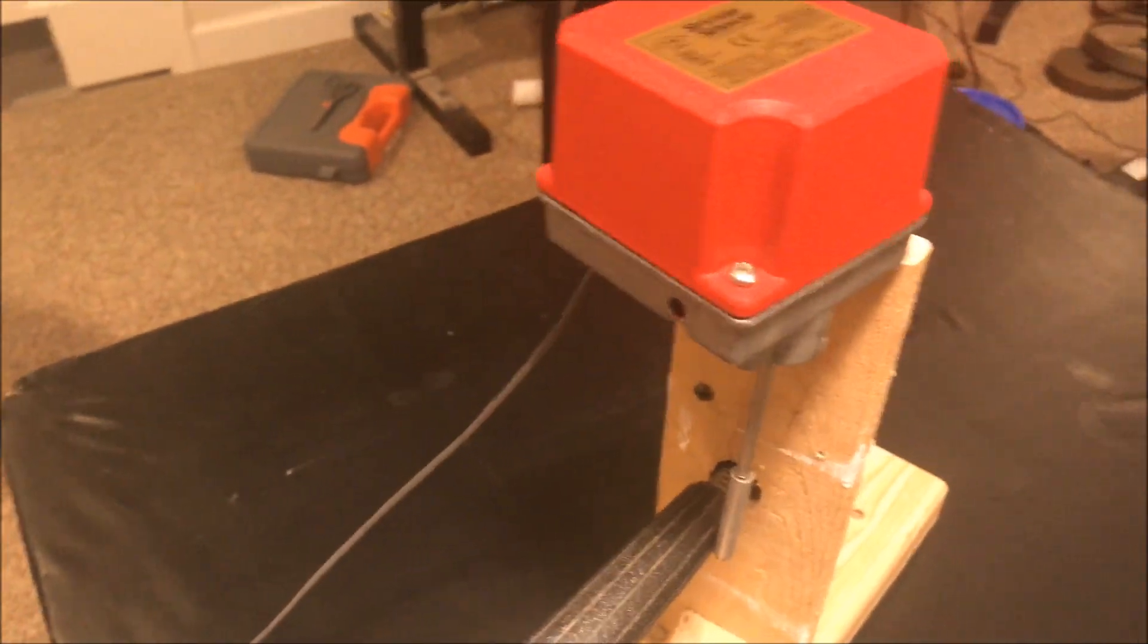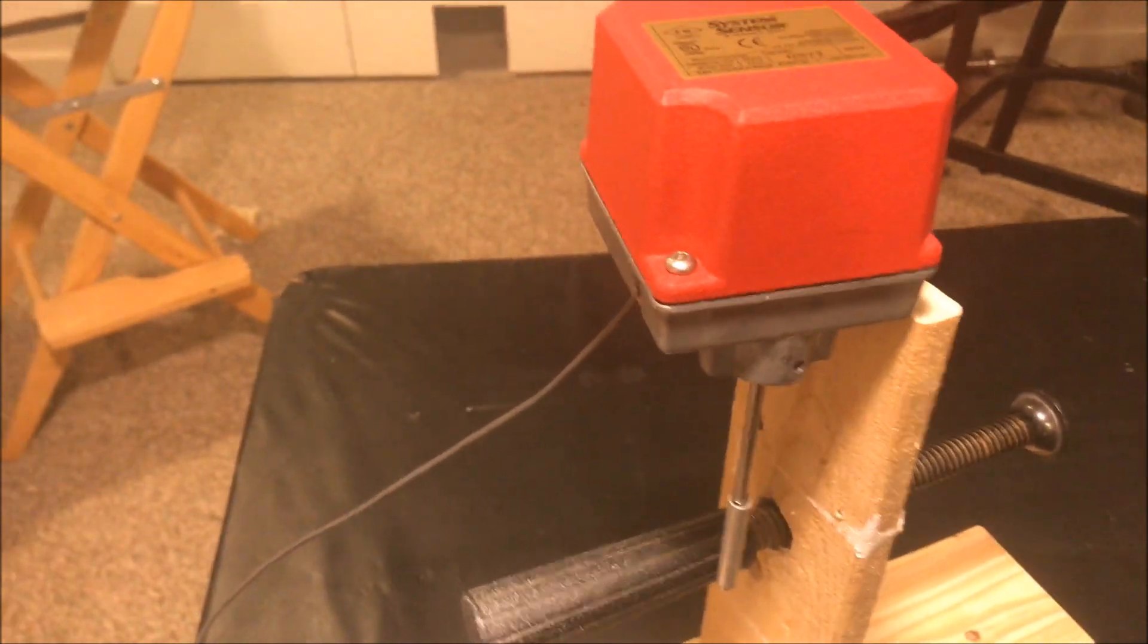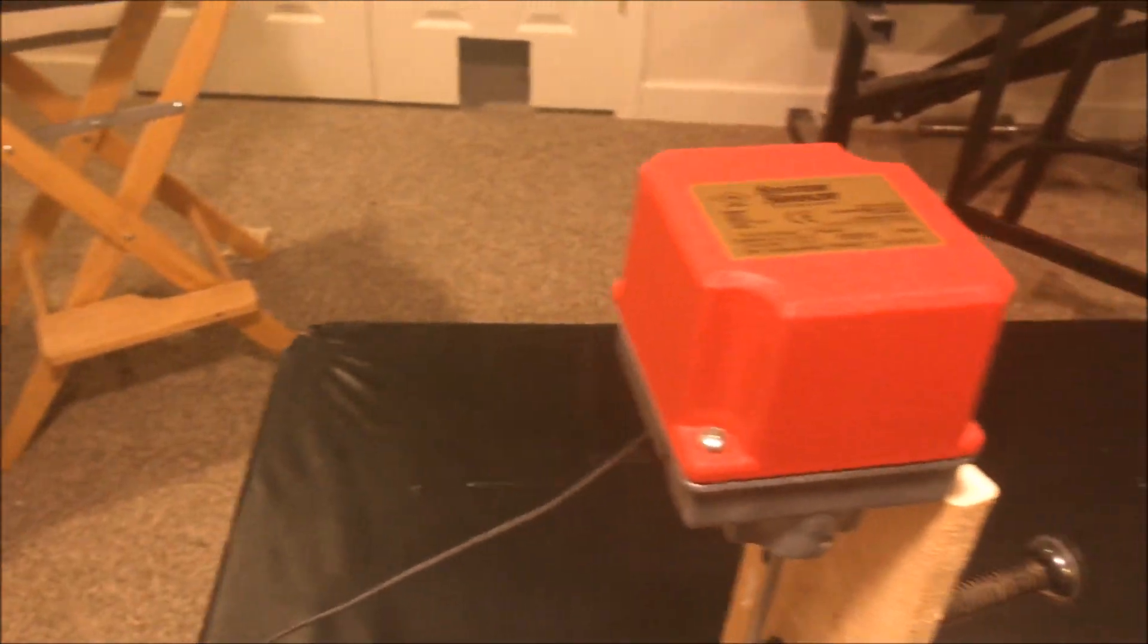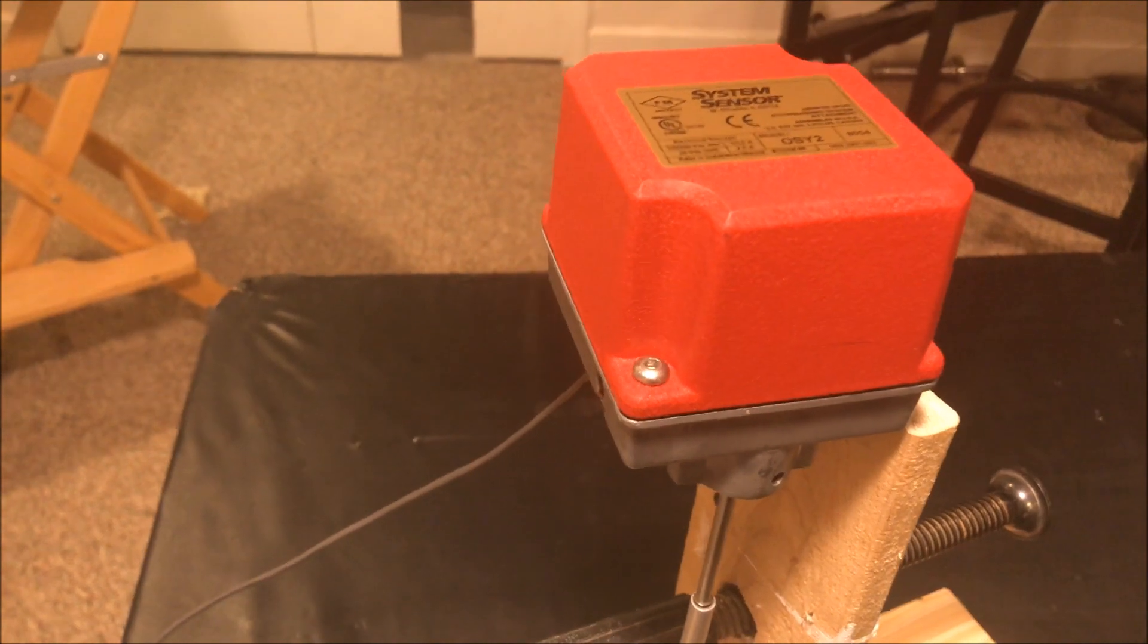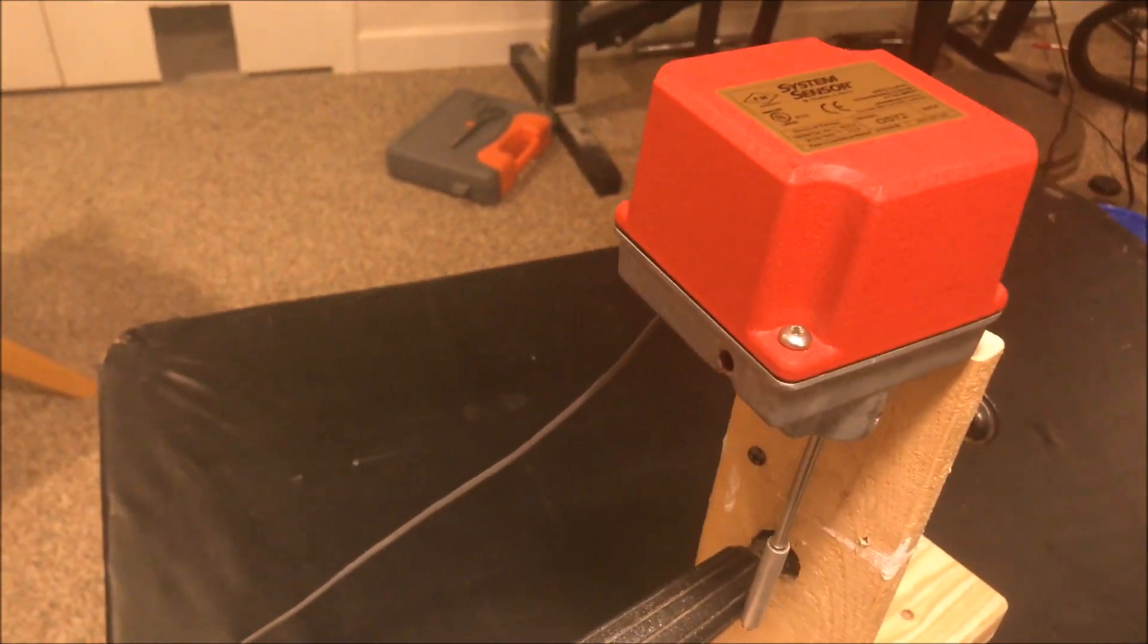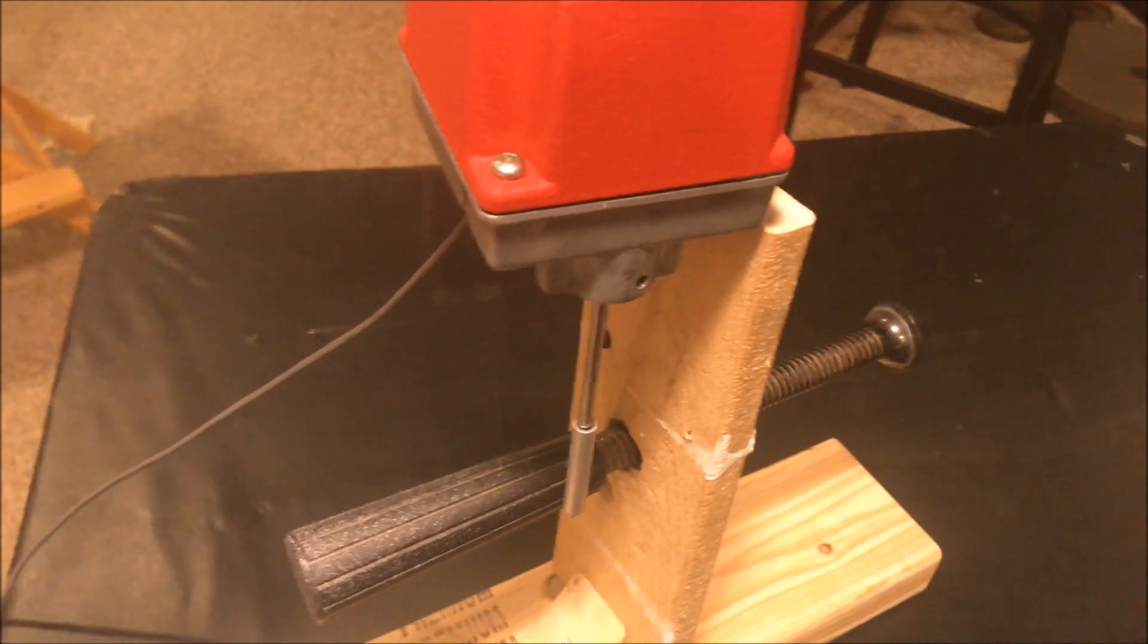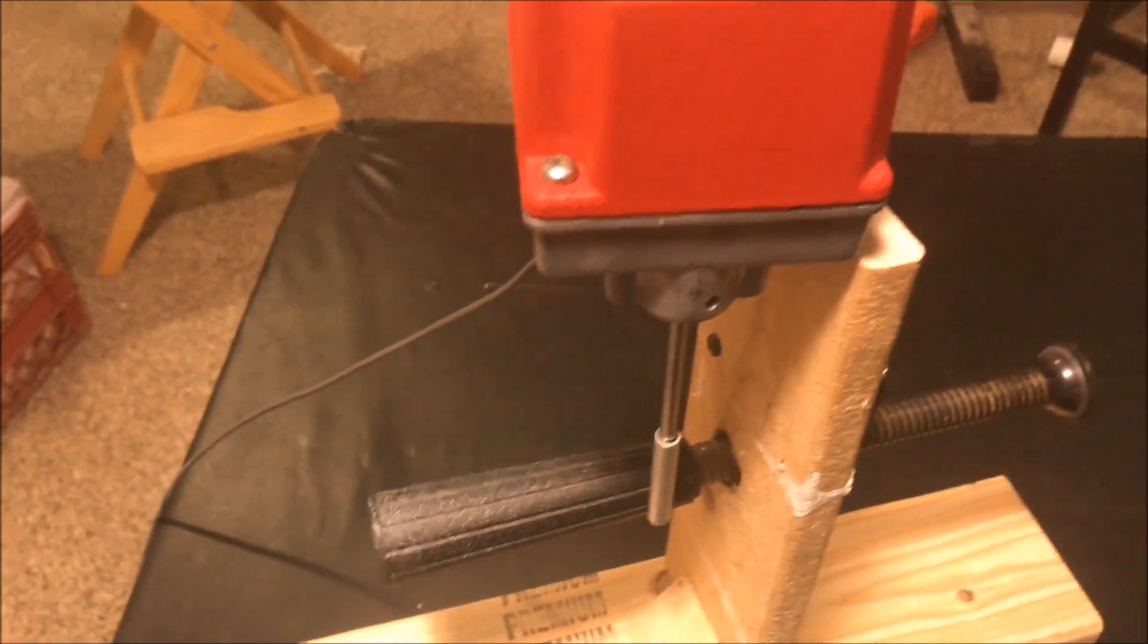Alright, so we got the switch back together. The panel is ready to go into supervisory, no alarms will sound. I know I have the key switch set for supervisory to have the NAC sound, that is not going to be happening today. It will just go into supervisory, thus mocking what a real system would. So say that we are going to open up the valve.